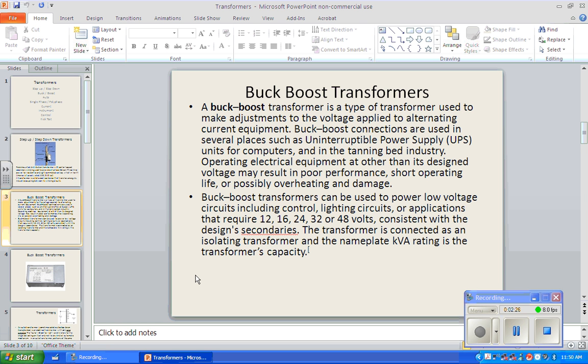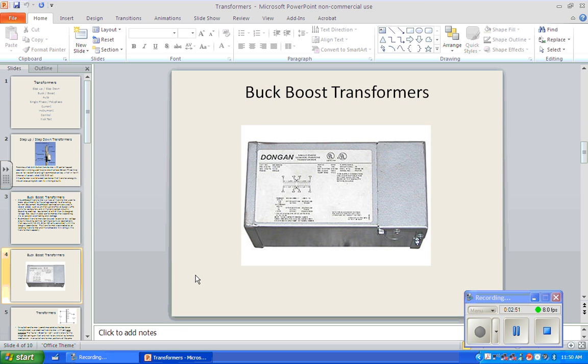Okay? And they're not used a lot of places, but they are used to trim the voltage to what the equipment needs. A lot of tanning beds that we have here in the United States came from Europe, which is a different frequency of power and a different voltage. And so sometimes we need a buck boost transformer to change the voltage to the exact needed voltage. So this is a small transformer. This is a buck boost transformer. You notice it has 4 taps on the top and 4 taps on the bottom. And so we can get different voltages with different wiring setups.